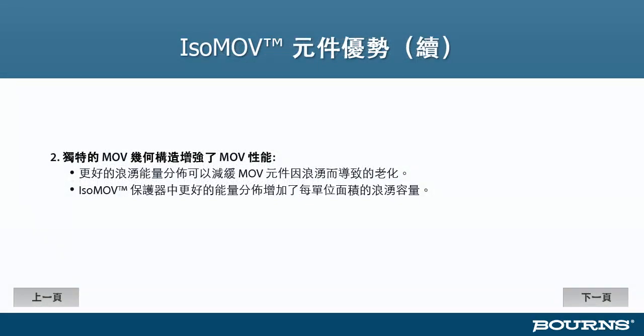Another aspect of the IsoMOV product design is the unique geometry of the MOV that funnels the current back into the center of the MOV and actually improves the MOV's performance. In fact, it almost doubles the surge capability of the MOV. The gas discharge tube has plenty of surge capability for these ratings. So what you end up with is a component that has a better surge rating than its MOV counterpart of the same size, due to the better distribution in surge energy. Because of the simple construction of this device and the presence of the GDT, we can extend the operating temperature range of normal MOVs. Even when an IsoMOV device is operating at higher temperatures, that increased leakage current that you would normally see in an MOV simply doesn't exist.